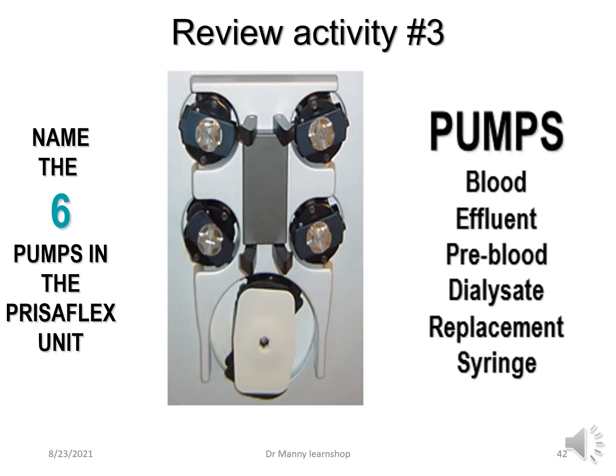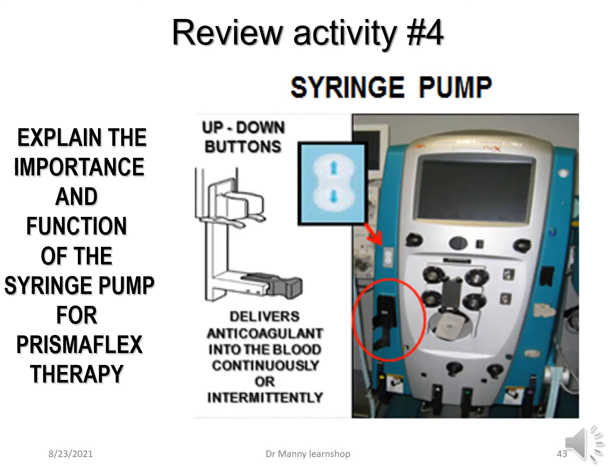Can you name the 6 pumps in the Prismaflex unit? The 6 pumps are the blood pump, the effluent pump, the pre-blood pump, the dialysate pump, the replacement pump and the syringe pump. What about the importance and function of the syringe pump for Prismaflex therapy? Well, the syringe pump is important to deliver anticoagulant, and this can be done either continuously or intermittently.